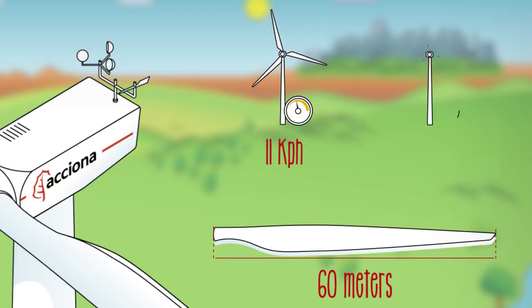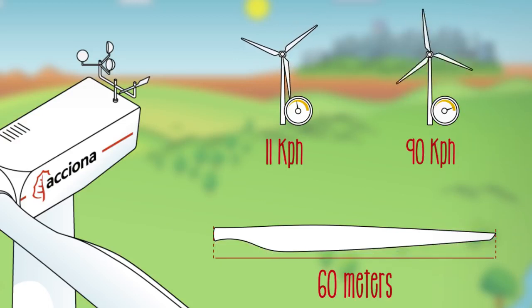With very strong winds, above 90 kilometers per hour, the blades are placed in the feathered position and the turbine stops spinning for safety reasons.